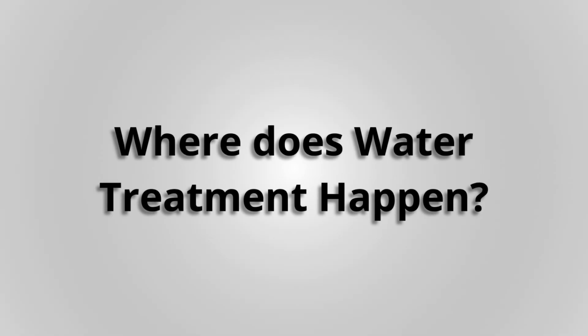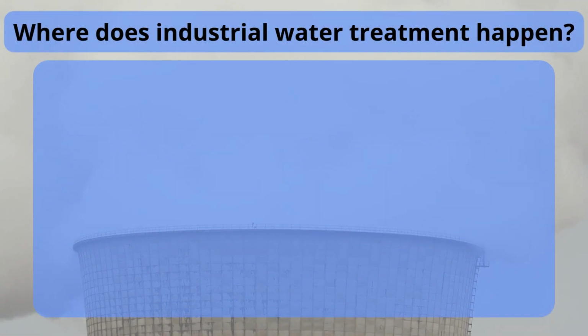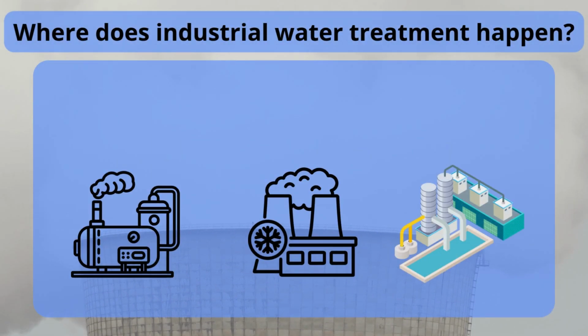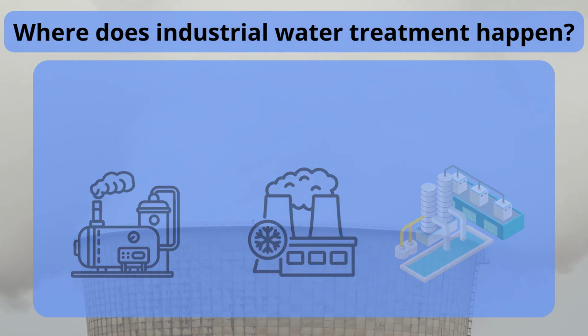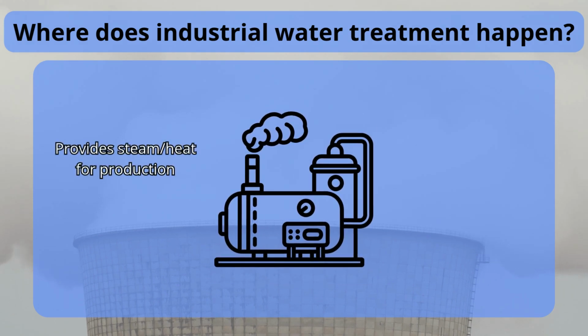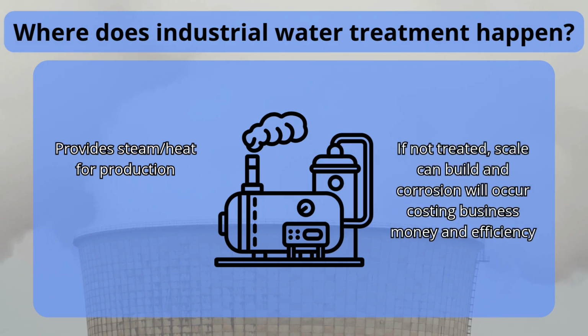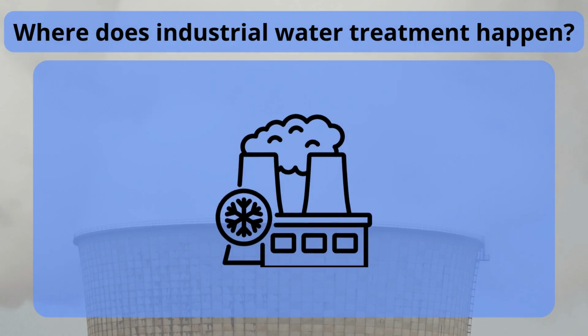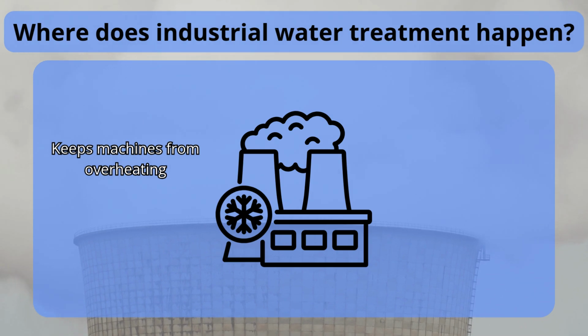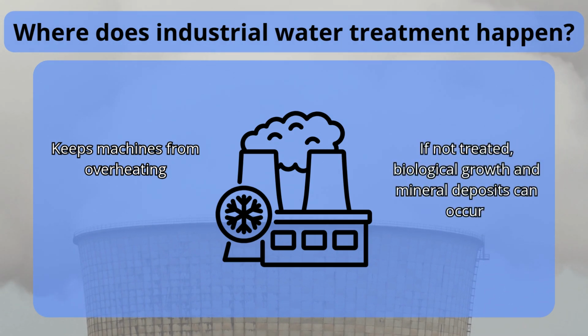So where does industrial water treatment actually take place? The most common applications are in boilers, cooling towers, and closed-loop systems. Each of these plays a critical role in keeping a facility running, and each one depends on properly treated water. Boilers generate the steam and heat that power production processes, but without treatment, scale and corrosion reduce efficiency and damage equipment. Cooling towers keep plants from overheating, but they're especially vulnerable to biological growth and mineral deposits if water isn't carefully managed.